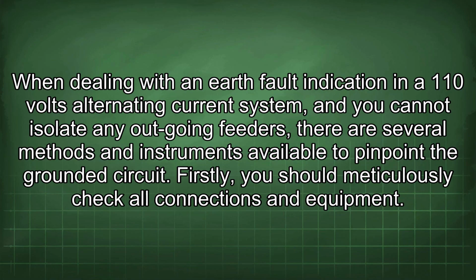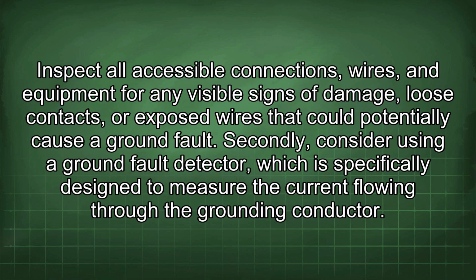When dealing with an earth fault indication in a 110 volt alternating current system, and you cannot isolate any outgoing feeders, there are several methods and instruments available to pinpoint the grounded circuit. Firstly, you should meticulously check all connections and equipment. Inspect all accessible connections, wires, and equipment for any visible signs of damage, loose contacts, or exposed wires that could potentially cause a ground fault.